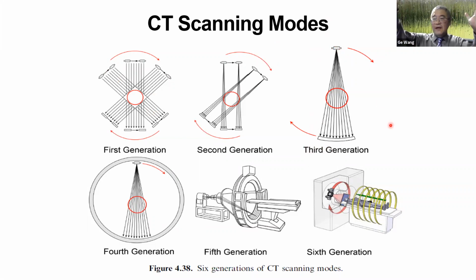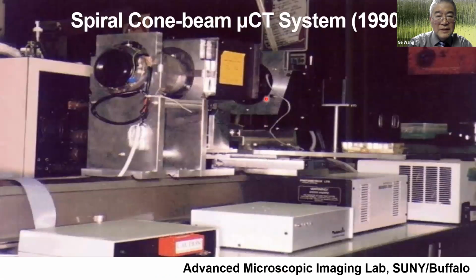And also, when you collect data, you rotate the source and detector ensemble around the patient. At the same time, you could translate the patient continuously into the gantry. So this is a helical spiral imaging mode. And the detector can be expanded from a one-dimensional detector array to two-dimensional. Then the fan beam becomes a cone beam geometry.